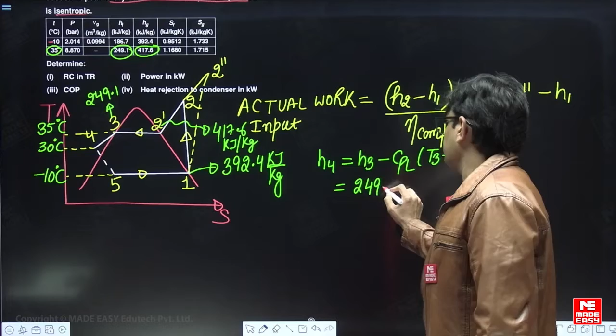What is the value of H3? H3 is 249.1 minus Cp of liquid. The Cp of liquid is given as 1.458 into subcooling, which is 5 degrees. So 249.1 minus 1.458 into 5. This value comes out as 241.81 kilojoule per kg.